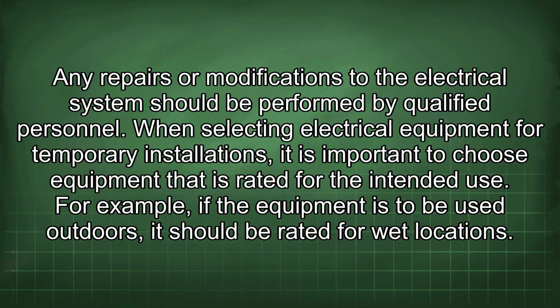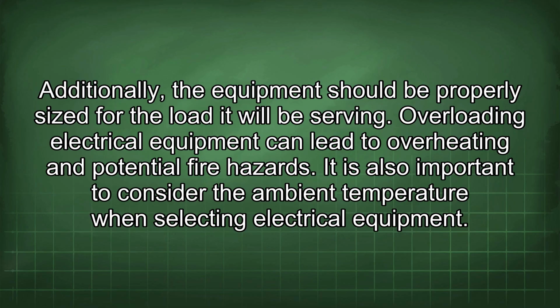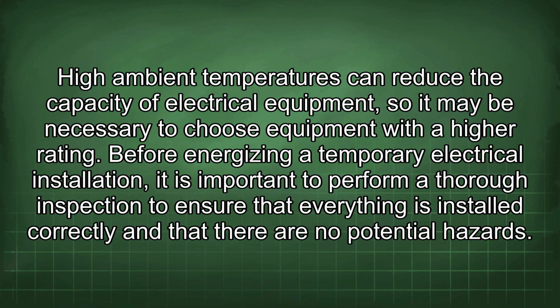Any repairs or modifications to the electrical system should be performed by qualified personnel. When selecting electrical equipment for temporary installations, it is important to choose equipment that is rated for the intended use. For example, if the equipment is to be used outdoors, it should be rated for wet locations. Additionally, the equipment should be properly sized for the load it will be serving. Overloading electrical equipment can lead to overheating and potential fire hazard. It is also important to consider the ambient temperature when selecting electrical equipment. High ambient temperatures can reduce the capacity of electrical equipment, so it may be necessary to choose equipment with a higher rating.